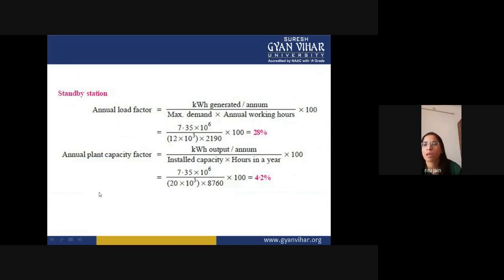Okay. Now, the annual plant capacity factor. The formula is average load divided by installed capacity. Average load can be written in terms of units. The installed capacity is your 20 megawatt for your standby station, and it can be calculated by this formula. So the plant capacity factor is your 4.2%.